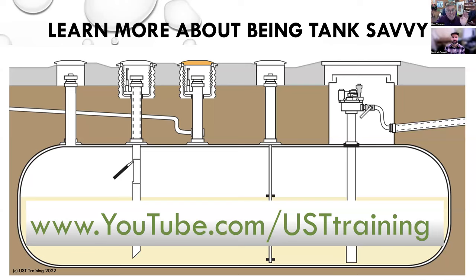After that, we can't guarantee this information is accurate. Some smarty pants contractor cut the length of the pipe in half in the programming. So it was passing a leak test, but it was not correct. When you have an electronic line leak detector, it has to be programmed for the pipe diameter, pipe length, and pipe type. If you have flexible plastic piping, it takes a bit more for stuff to stabilize. Thank you for that, Vicky.